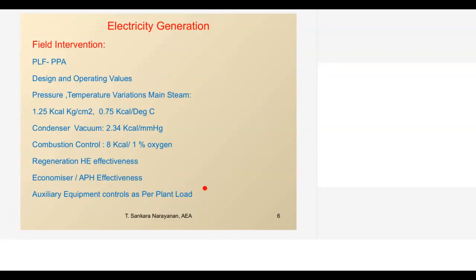See, normally in a power plant we have not come up against these problems, but today, because of surplus power, most of the units have to run with a lower PLF. So when PLF is reduced, how the auxiliary system capacity control works has to be reviewed. So we can discuss all these things. But in a power plant, when you want to attempt certain changes, it has its own time.